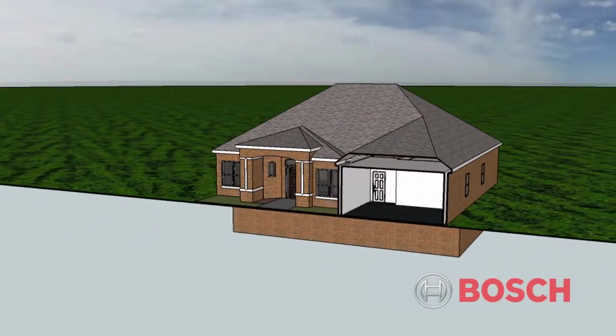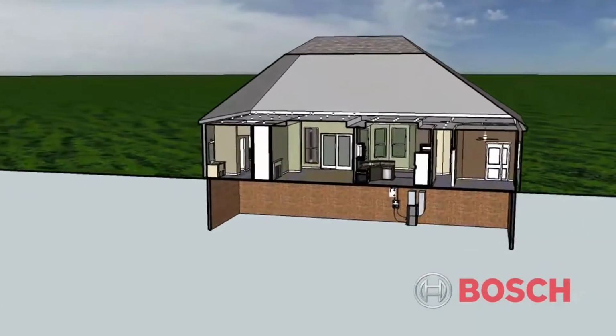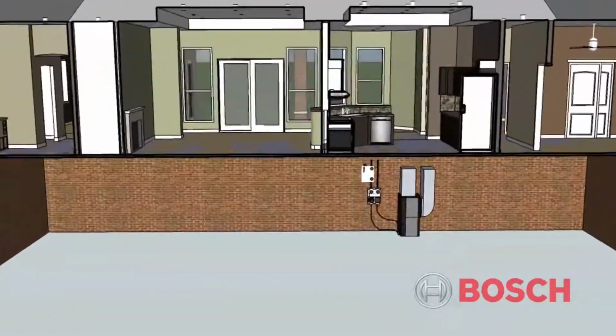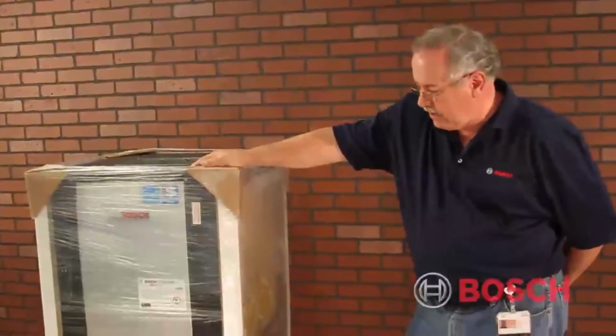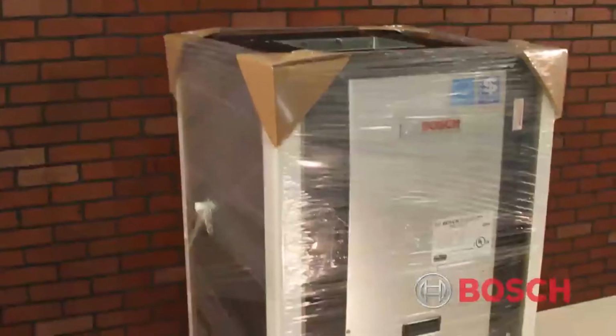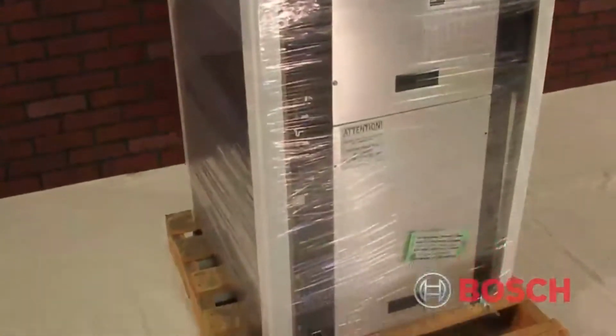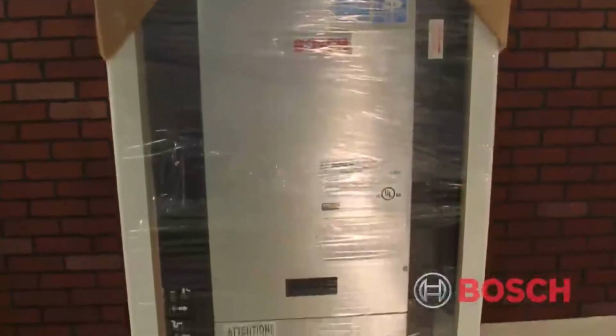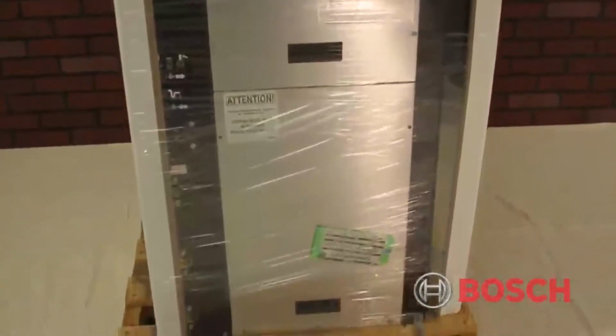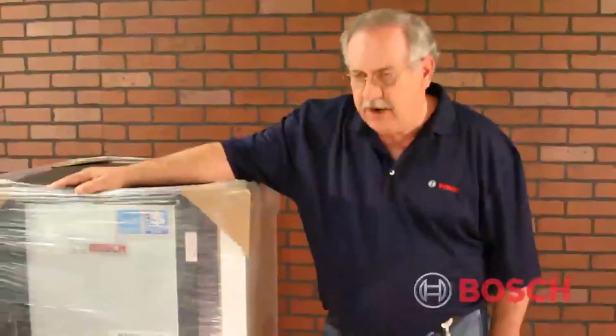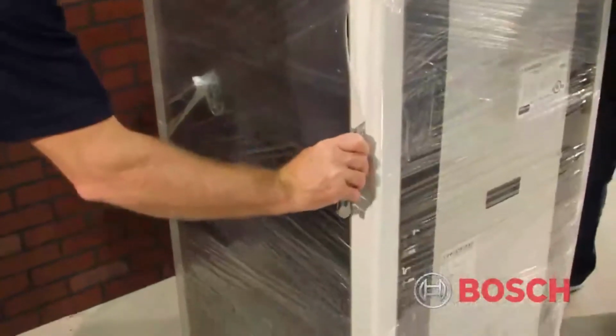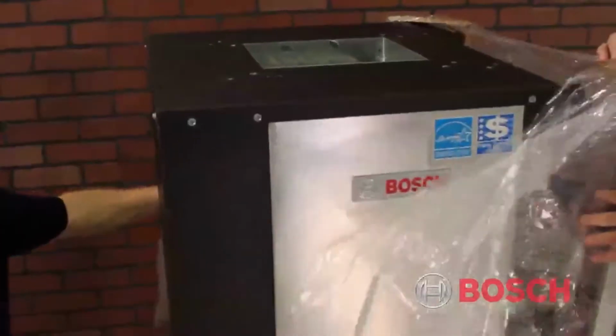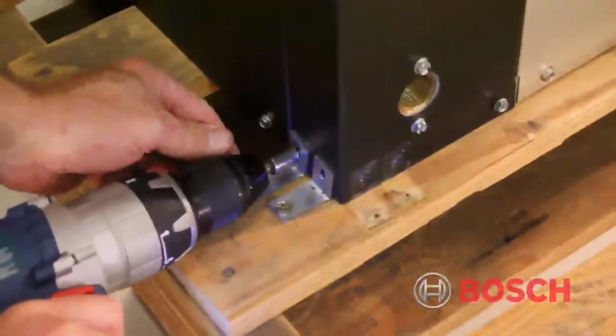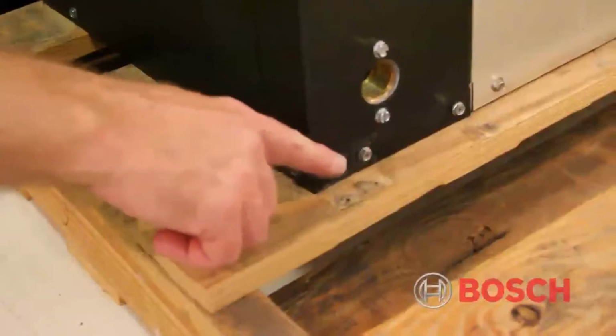We're going to take you through an installation of a TA-025 Bosch geothermal unit. So here we have received a Bosch TA-025 geothermal heat pump at the site. Our first step is to check the machine as it was shipped on the pallet to make sure that we have no visible damage. Our next step will be to remove all of the shipping materials, the packaging and the wrap, and remove the machine from the pallet.